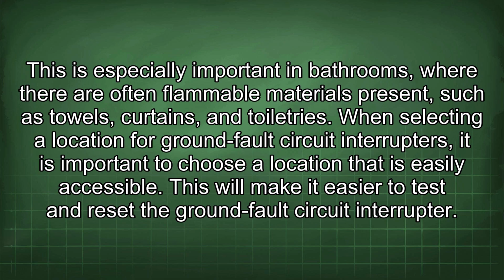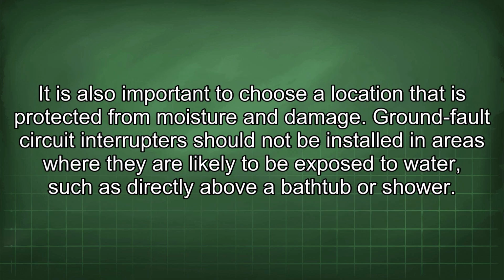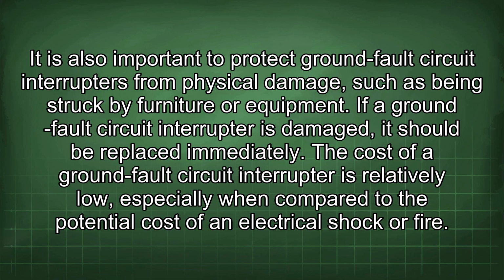When selecting a location for ground fault circuit interrupters, it is important to choose a location that is easily accessible. This will make it easier to test and reset the ground fault circuit interrupter. It is also important to choose a location that is protected from moisture and damage. Ground fault circuit interrupters should not be installed in areas where they are likely to be exposed to water, such as directly above a bathtub or shower. It is also important to protect ground fault circuit interrupters from physical damage, such as being struck by furniture or equipment. If a ground fault circuit interrupter is damaged, it should be replaced immediately.